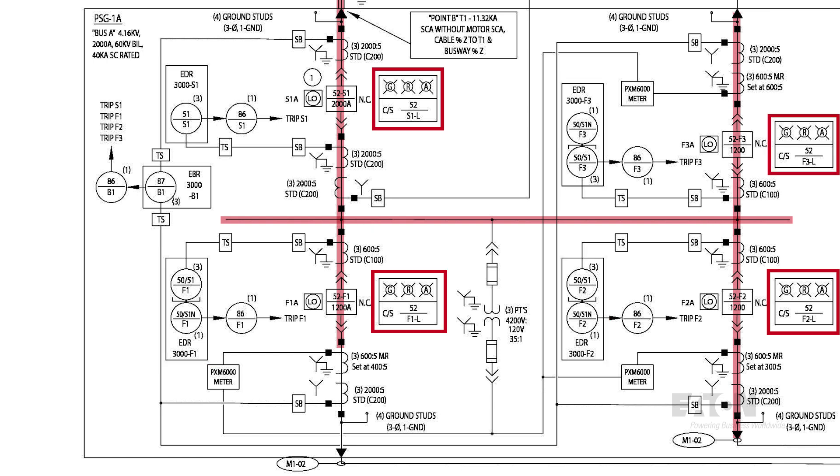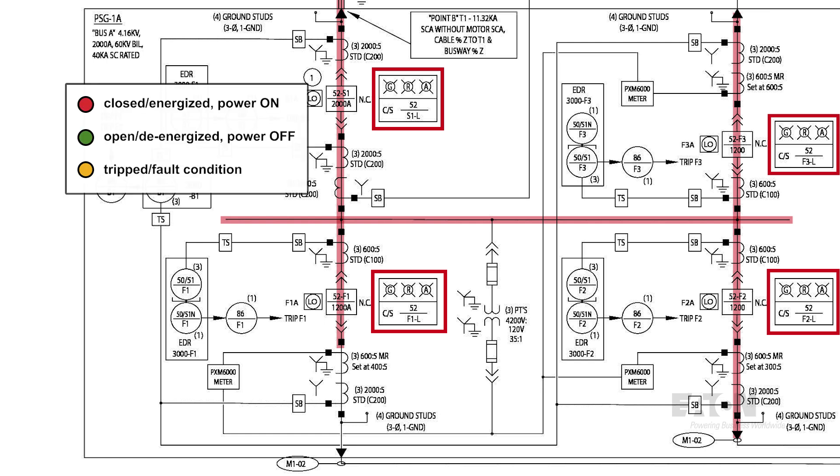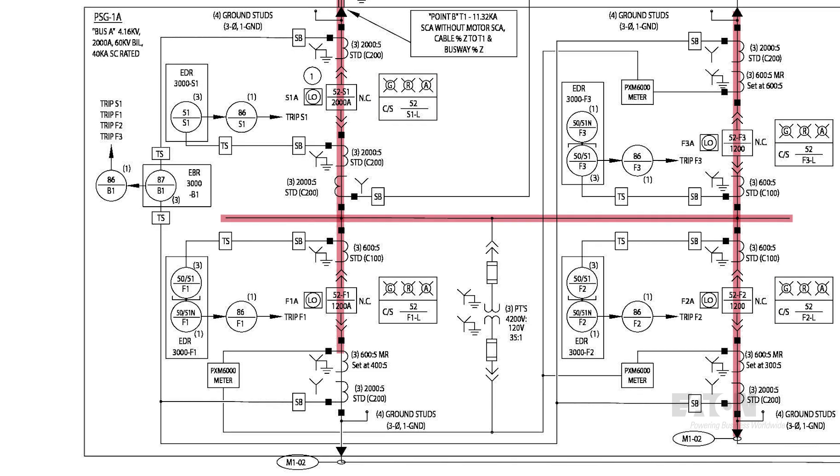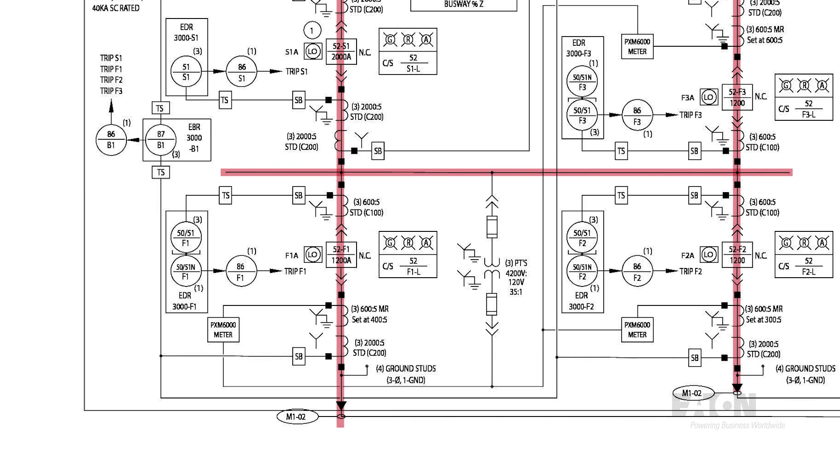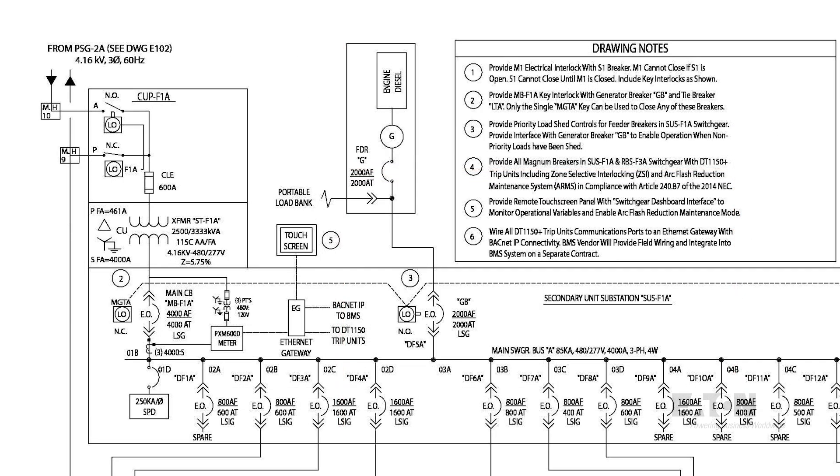Each breaker in the 4160 volt lineup has CTs feeding an EDR3000 relay, a control switch, and red, green, and amber indicating lights. When illuminated, the red light indicates the breaker is closed, the green light indicates the breaker is open, and the amber light indicates the breaker has tripped due to a fault on the system. This is the standard color scheme for power systems. Red means the circuit breaker is closed and power is on, and we need to stop and take caution. This is the opposite of what many may anticipate. Let's keep following the power flow. Feeder M1-02 extends onto the next page.